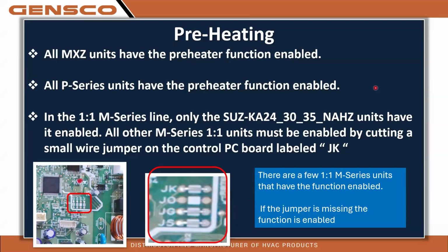If you can't wait 12 hours, you could put a heat gun to the bottom of the compressor and begin heating it. Mitsubishi has actually tested how long that would take to adequately heat the oil in a compressor, and they came back with 2.5 hours of heat gun. And again, the first time you run this unit is the most important moment in its entire existence. So this is a huge, huge thing in our world that we want to see done before you start compressors.